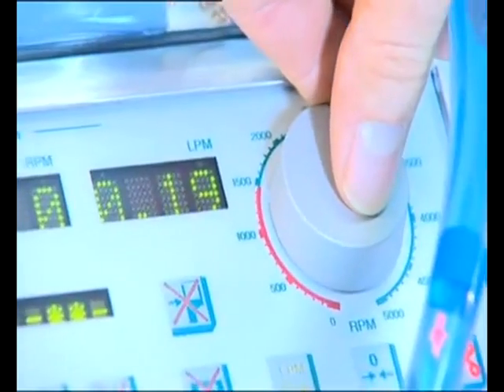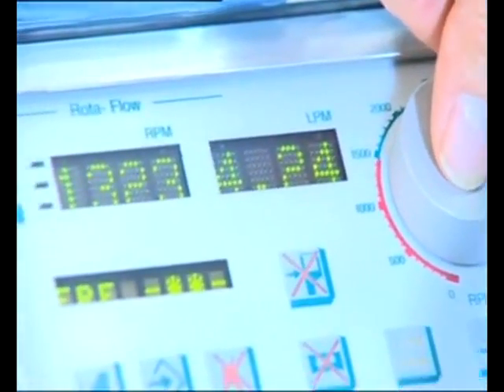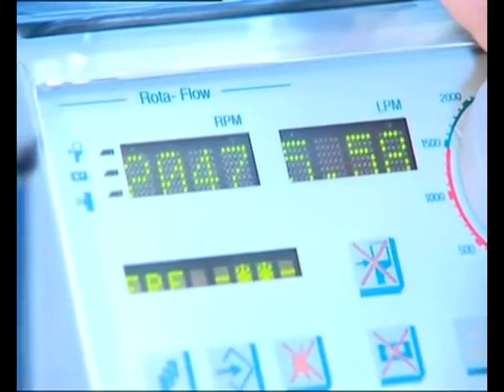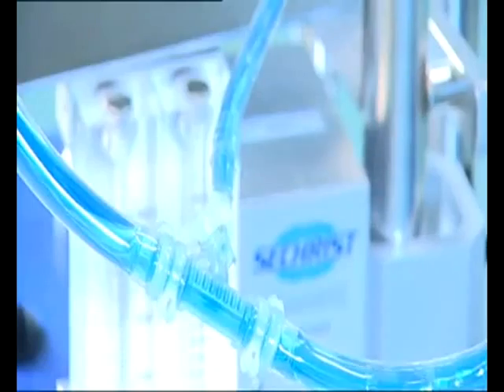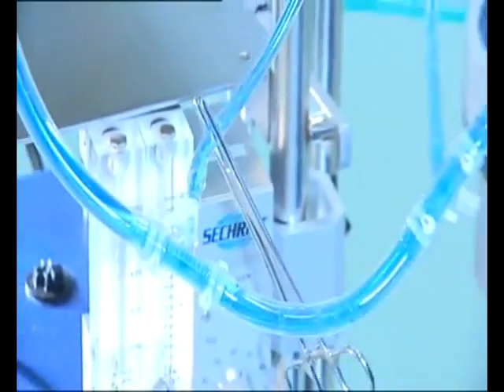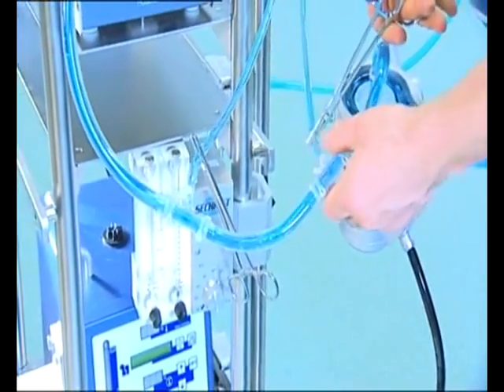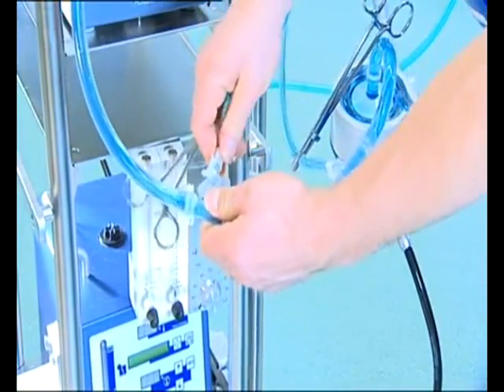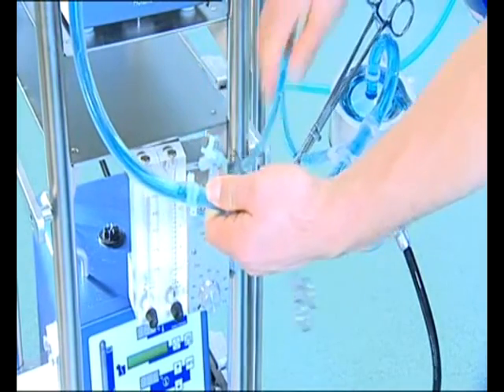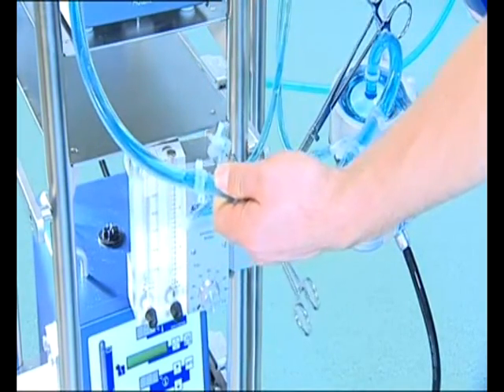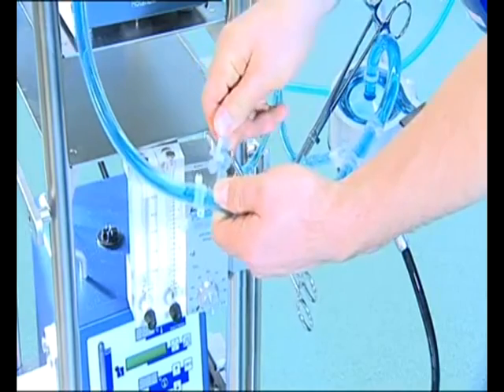Solution is now flowing through the entire system, and the Rotaflow centrifugal pump speed can be increased to a high flow. The priming lines are no longer required and can be removed. To be on the safe side, the three-way stopcocks can also be disconnected and closed in a sterile way with the luer caps.